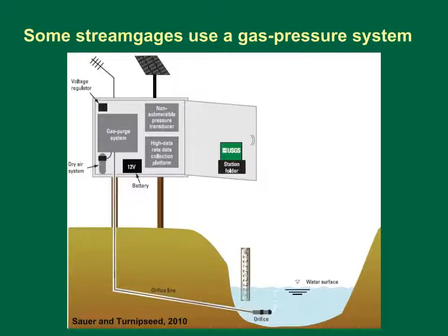This schematic diagram shows a stream gauge with a gas pressure system. In this type of gauge, gas is bubbled out of an orifice near the bottom of the stream, and the amount of pressure needed to maintain flow of the gas indicates the depth of water above the orifice. A non-submersible pressure transducer is used to translate pressure measurements to an electronic record of stream stage. As with the previous stream gauge, the electronics are powered by a solar battery system, and measurement results are transmitted via satellite or cell phone. This stream gauge has an outside staff gauge mounted to the stream that is used to manually check the water level to help calibrate the pressure sensor measurement.